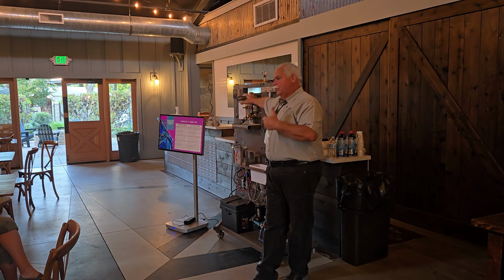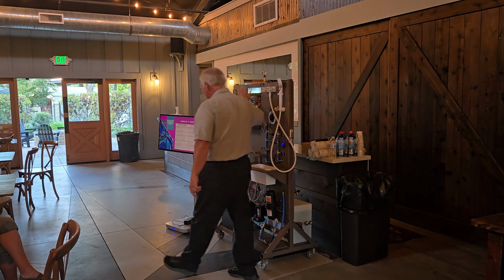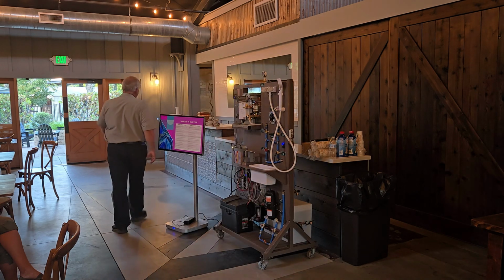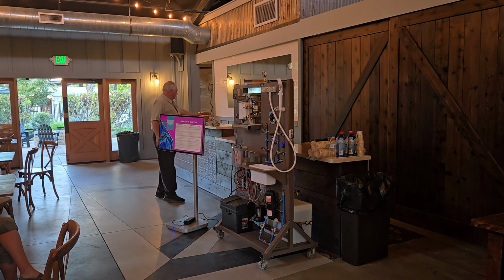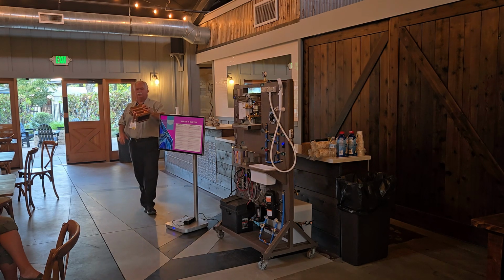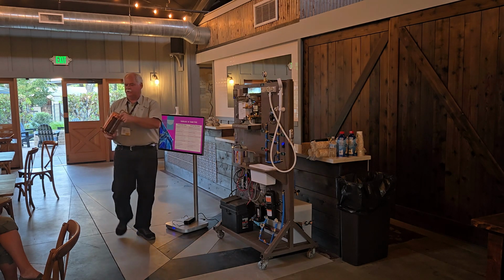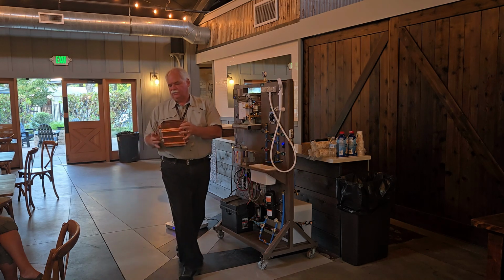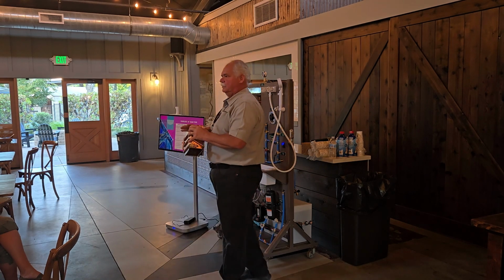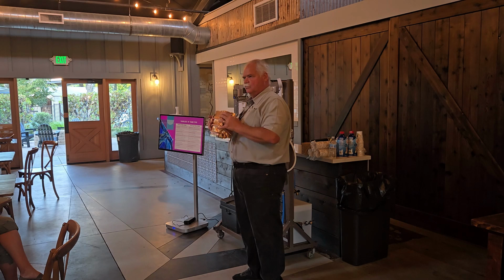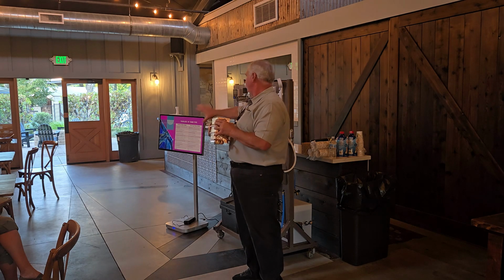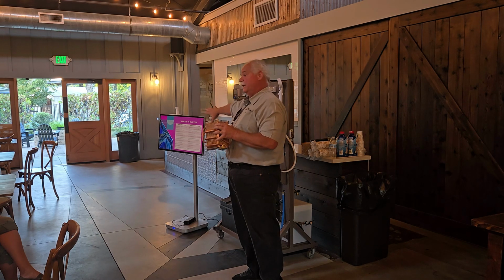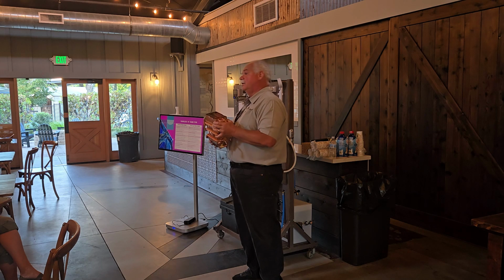But if I don't have enough water running through these coils, I can't turn that burner down. This is actually what my heat exchanger looks like. I can't turn that burner down enough to keep the water temperature below whatever it's preset to. I'm going to demonstrate that.